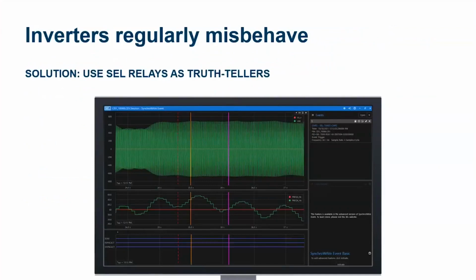Here's an example. Here's a plot taken from an SEL 700G relay, and it shows large, and this is from an event report that extracted out and now is displayed on SynchroWAVE Event, one of our softwares. This shows an unacceptable frequency oscillation. You see it in the second plot, the middle plot. You see an oscillation in frequency. Now, this caused a lot of finger pointing on this particular job as to whose fault it was. Was it the inverter? Was it the generator? Was it the AVR? Was it the governor? Was it the fuel supply?